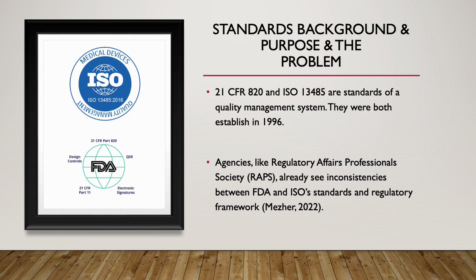Without prescribing a specific method for establishing these features, the FDA has defined in the QS regulation the basic elements of what a quality system shall incorporate. The same year the FDA published 21 CFR 820, ISO published ISO 13485, a quality management system for medical devices, which are requirements for establishing and maintaining a quality system as well. ISO 13485 is divided into 8 clauses.